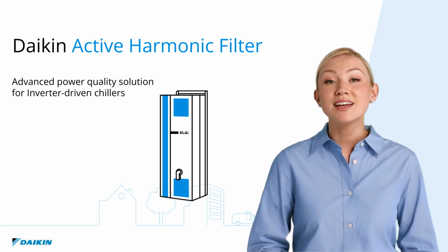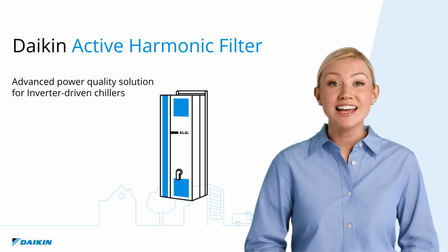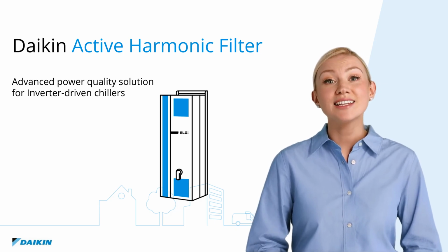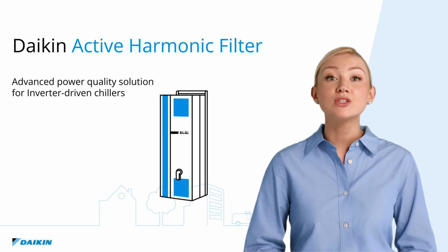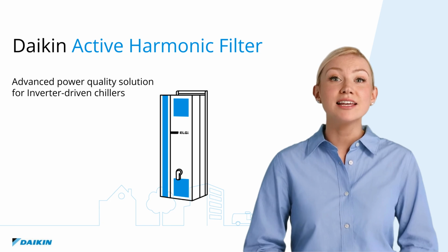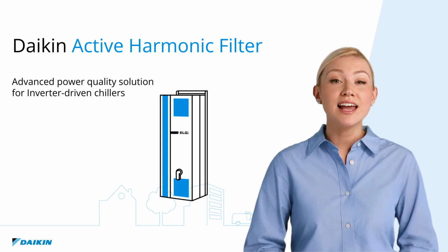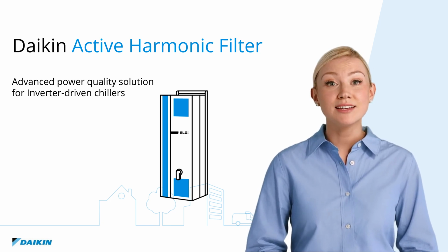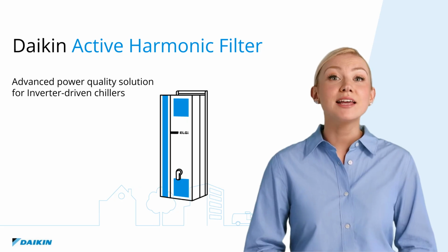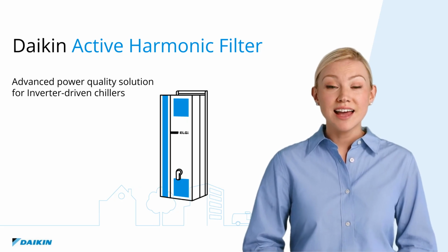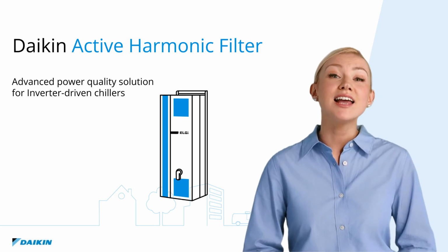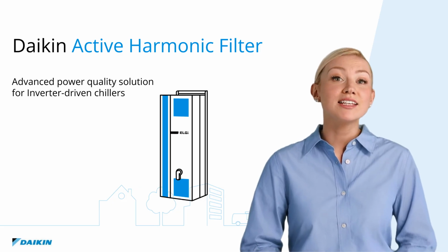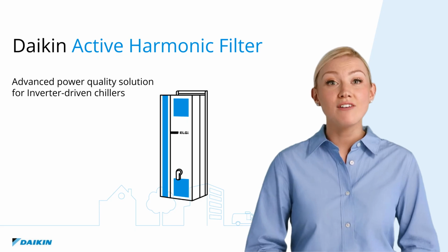In this episode of our series, we will explore a topic that's often overlooked, but vital to the long-term reliability and cost-effectiveness of data center infrastructure: harmonic distortion. Electrical disturbances within the system lead to tripped protection devices, overheating cables, server interference, and, over time, increased maintenance costs. That's where harmonic mitigation becomes critical, and Daikin has developed a truly elegant integrated solution that takes a lot of the usual complexity off the table.